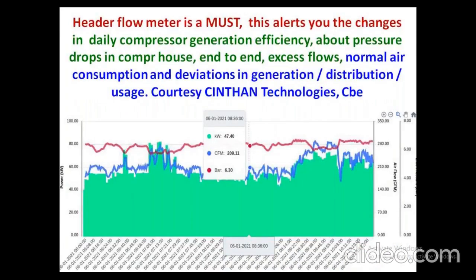Thanks to CINTHAN Technologies. The way I'm telling all the OEMs also, compressed air flow metering, everyone was thinking it is a taboo. It was costing more than 2 lakhs, 3 lakhs. Now it has become affordable. It is available for 1 lakh. See, this textile mill was operating a 37 kilowatt machine at 47 kilowatt. You can see the 47 kilowatt because they did not have a cleaning receiver. Because they did not have the cleaning receiver, once the cleaning is taken, straight away the pressure drops.